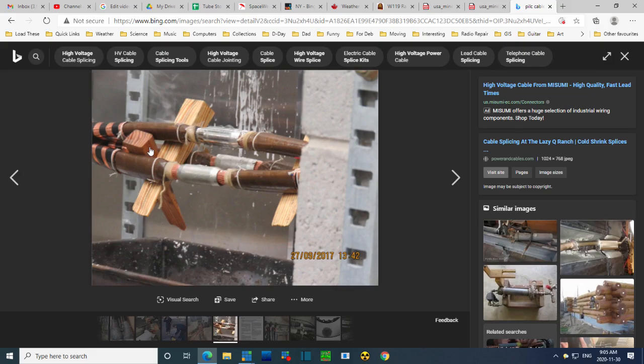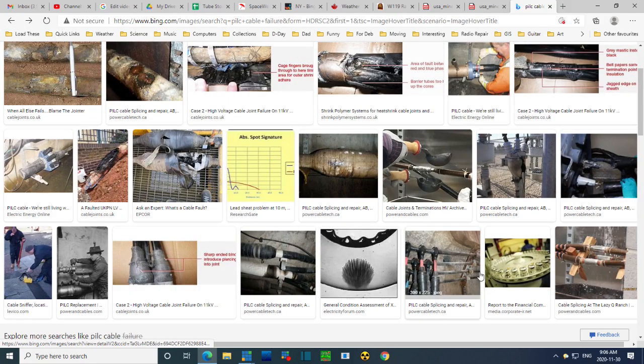Paper insulated cable. You can bend these cables because in these paper lappings there are little gaps. And as you bend the cable, the gaps will close. As long as you don't bend it too far, the paper won't crash into itself. There's a certain amount of flexibility in this huge cable. See the strands are twisted? Well, the whole cable, each individual phase, is also twisting down the cable. All this to try to build some kind of flexibility. There you can see the shield back here, the metal shield on it. Well, I get very excited looking at this stuff. Let's see what else we can find. Maybe we'll find some blown cables here in a minute.